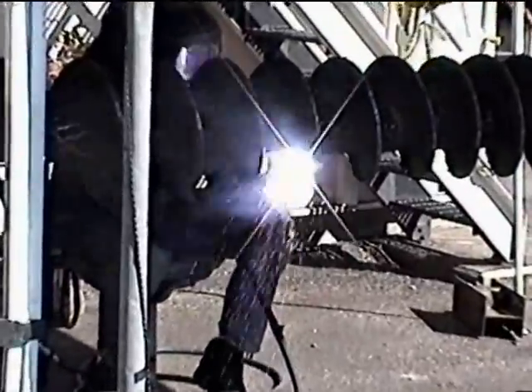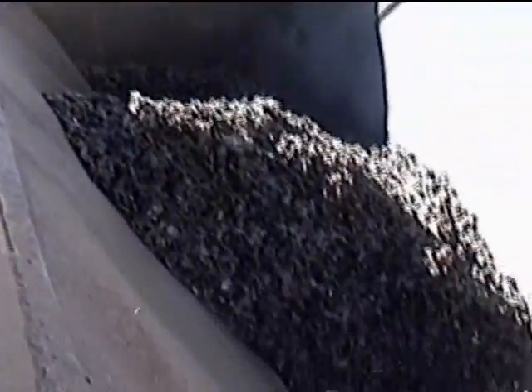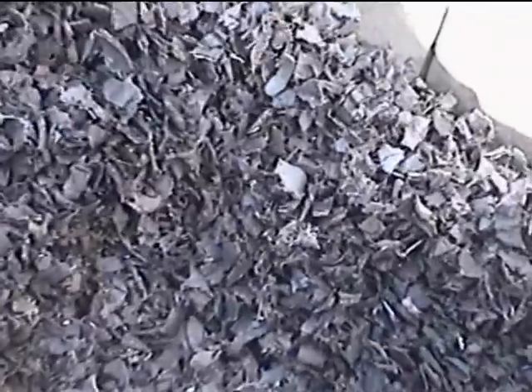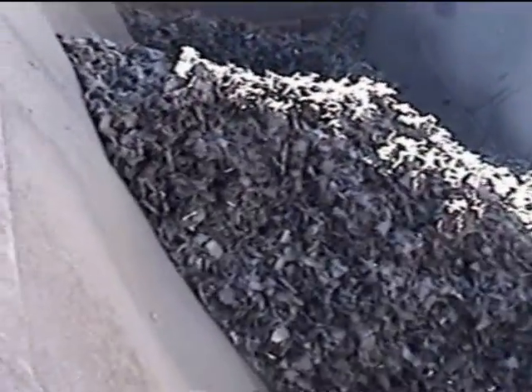This would be wood chips only, or wood chips and tires? We've got a little bit of tires mixed in — I want to say about 10%, give or take, of tire chips. And the tire chips are quite abrasive. They're full of wire, and the bead wire is extremely abrasive. Some of it is just bead wire, just like lathe bits — it's super abrasive. This is the highest abrasion auger we have here at the plant.